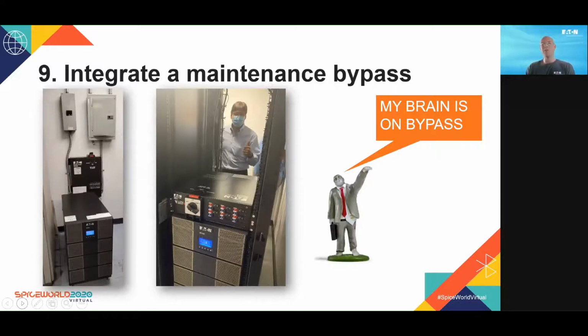Tip 9, integrate a maintenance bypass. We highly recommend configuring a UPS with a maintenance bypass so you can switch over to utility power without shutting down your equipment while servicing or replacing the UPS. The one shown here is for mid-sized models, but you can add them for smaller UPS units too. Maintenance bypasses are also integrated into power pass distribution modules, which are compatible with many of our single-phase UPS units.